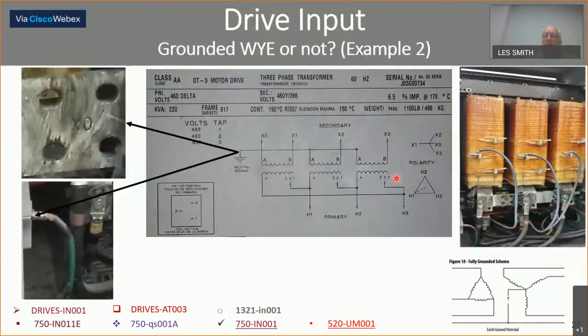Here's the second example. Remember this transformer here? Here's the XO, nothing attached to it. That's right here. However, you've got your ground wire coming in from the power attached to here. This is what the nameplate on the transformer said. Neutral is bonded right there. It wasn't. It's open like this.